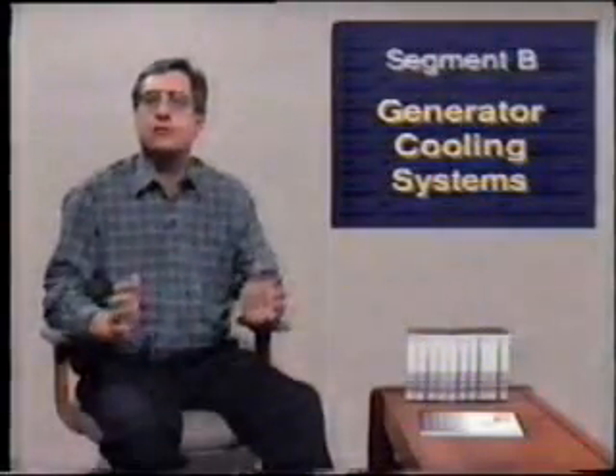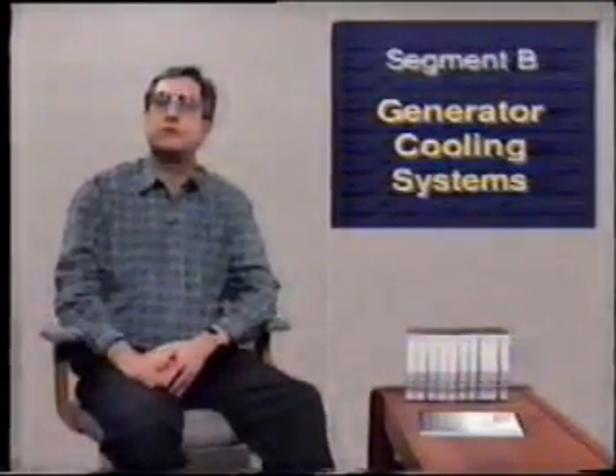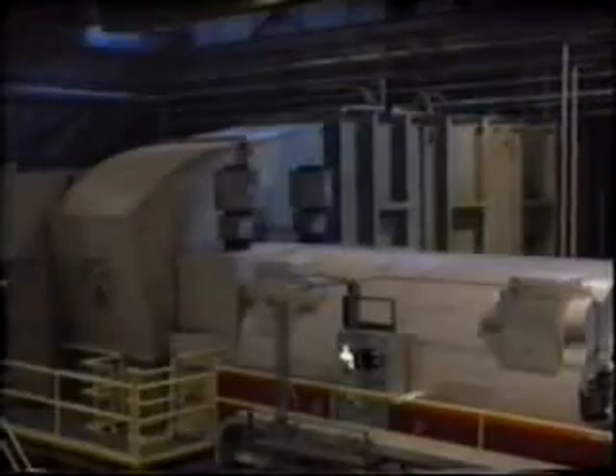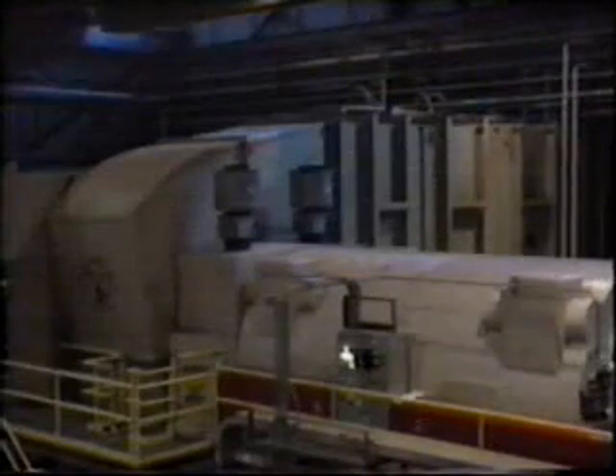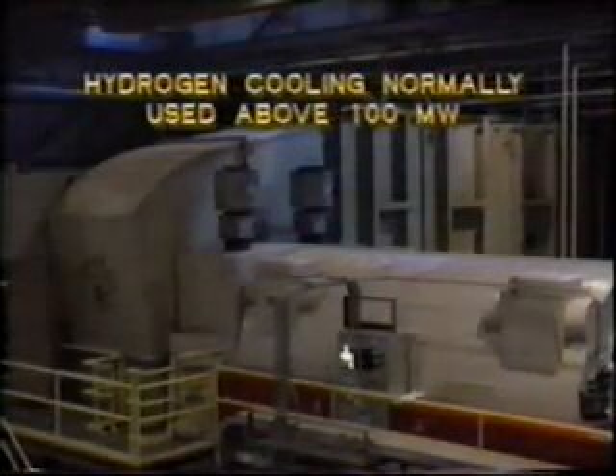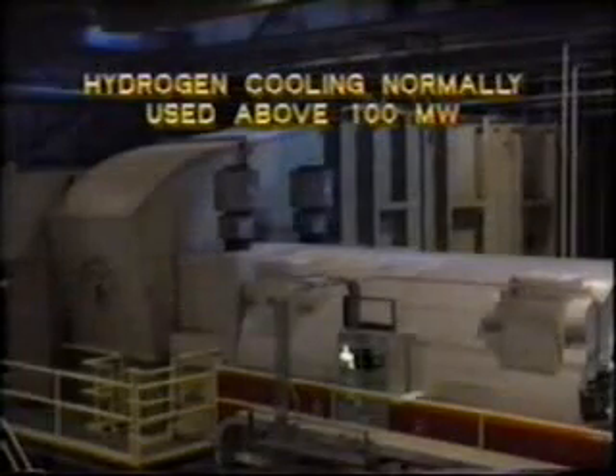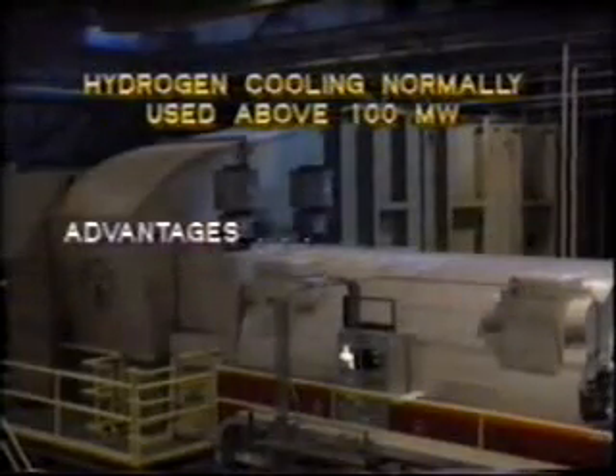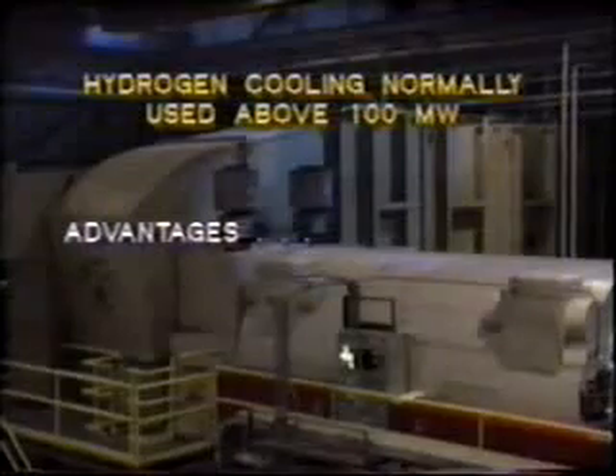As we have already mentioned, air cooling systems are used on most gas turbine generators. However, when the unit size increases above, say, 100 megawatts, then hydrogen cooling is normally employed. There are several advantages to using hydrogen as a cooling medium instead of air.